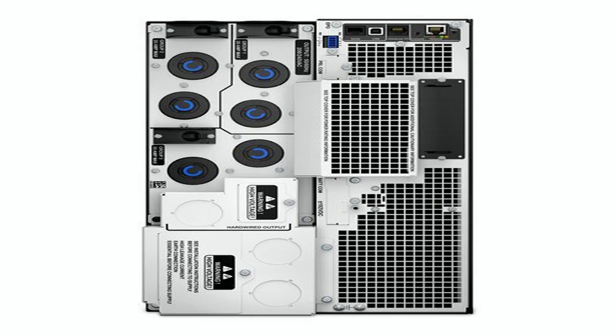The SRT8KXLT also isn't the best match for anyone who doesn't have the space for a rack-mountable unit or who can't provide the dedicated cooling that a 10 kVA unit generates. Those units can run warm, and while the intelligent management helps, you still need adequate airflow. Otherwise, you'll see the battery life shorten faster than the spec sheet promises.